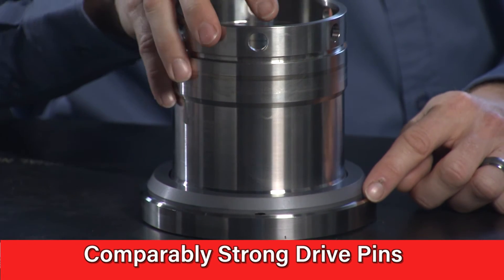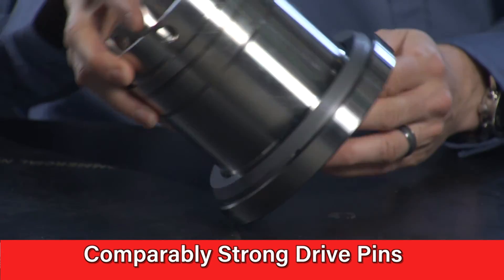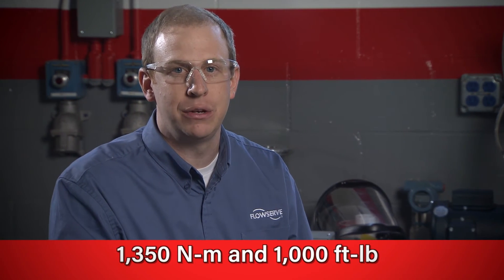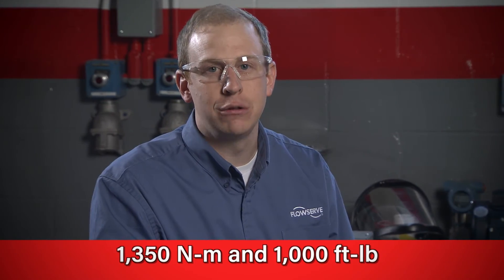Comparably strong drive pins engage in the opposing rotating seal face, and the combination of these high-torque features yields a torque capability of up to 1,350 newton meters, 1,000 foot-pounds.